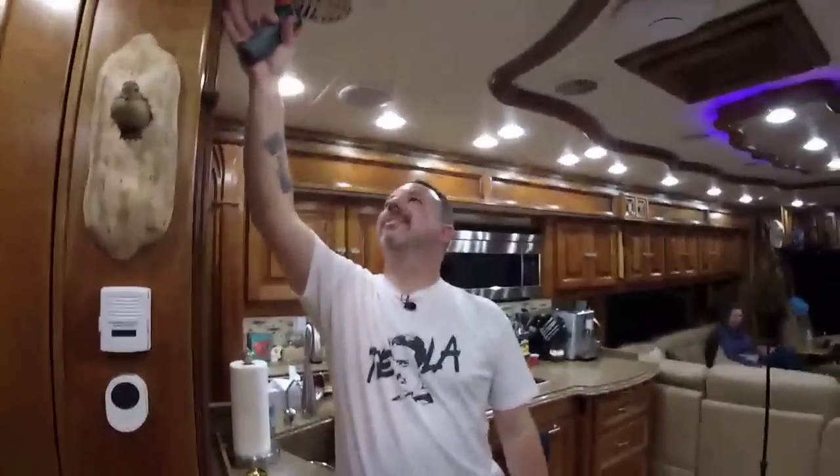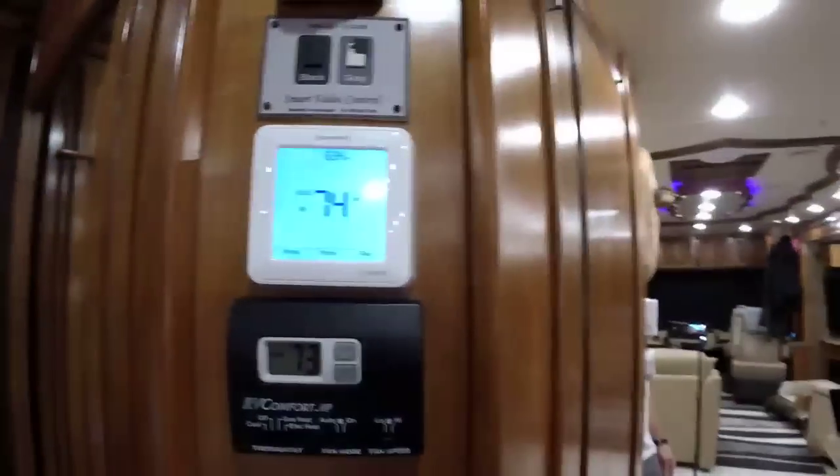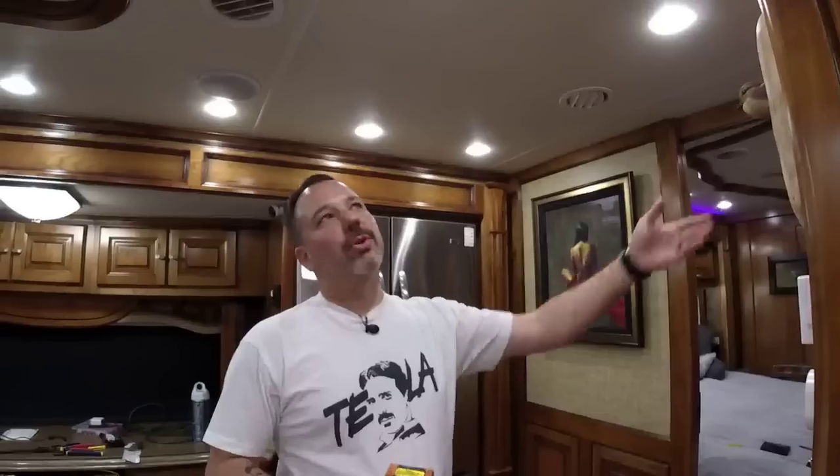Nah, you know, they're online and everything. Don't get me wrong. I'm just joking with them. So what's the reading up there, Michael? Just say what it's supposed to say. It's 70, whatever that says. Okay. This says 74. Yeah, this says 77. That's close enough, right? Yeah, it's pretty close. It's off. I did adjust the offset. It only allows a maximum of 3 degrees offset adjustment. So the rest is probably due to the wiring, or maybe I put a screw through the wire. Who knows? But it's close.